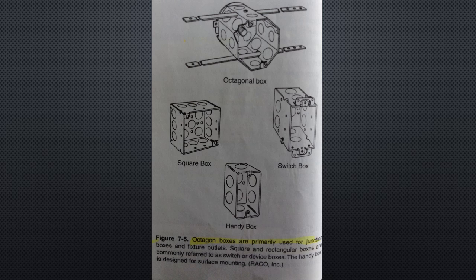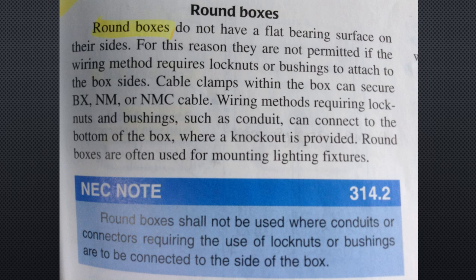Round boxes: round boxes do not have a flat bearing surface on their sides. For this reason, they're not permitted if the wiring method requires lock nuts or bushings to attach to the box sides. Cable clamps within the box can secure BX, NM, and NMC cable. Wiring methods requiring lock nuts and bushings, such as conduit, can connect to the bottom of the box where the knockout is provided. Round boxes are often used for mounting lighting fixtures. NEC note 314.2: round boxes shall not be used where conduit or connectors requiring the use of lock nuts or bushings are to be connected to the side of the box.